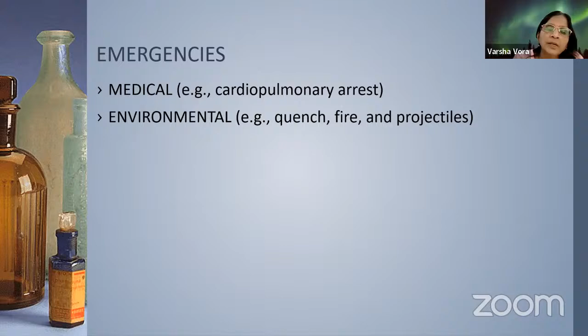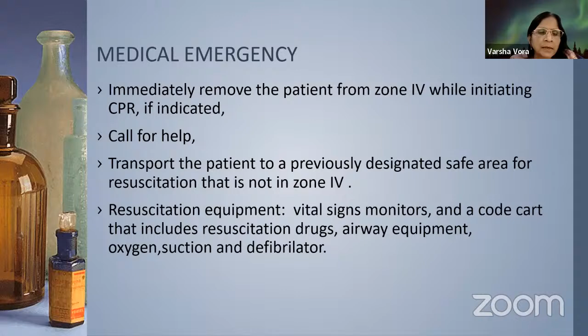Emergencies in the MRI room: medical emergencies like cardiopulmonary arrest, and environmental emergencies like quench, fire and projectiles. In a medical emergency, immediately remove the patient from zone 4 while initiating CPR if indicated. Call for help. Transport the patient to a previously designated safe area for resuscitation that is not in zone 4. The resuscitation cart should include vital signs monitors, resuscitation drugs, airway equipment, LMA, I-gel, oxygen, suction and a defibrillator.